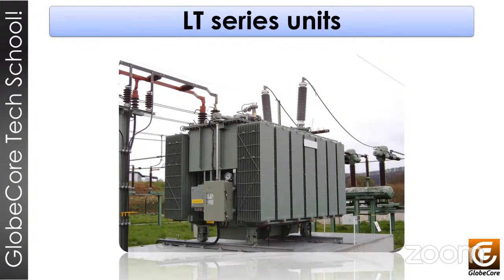Currently, enterprises use several dehydration methods. Sometimes the dehydration does not have the desired effect since it was carried out with insufficient understanding of the procedure being run. Removing moisture from a power transformer that has been used for a long time is a task that has been worked on for many years, and many times achieving optimal dehydration of a long-used power transformer without moving it is hard, since the operations are very expensive and sometimes no longer feasible.